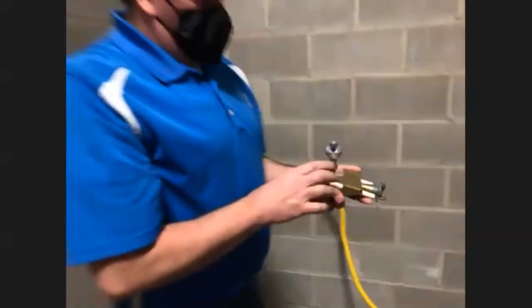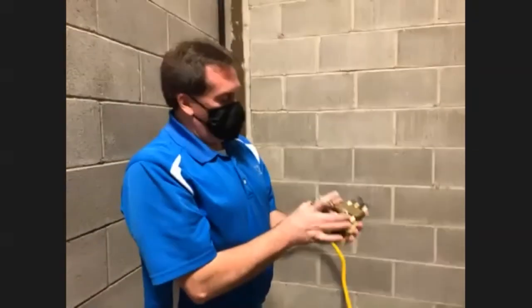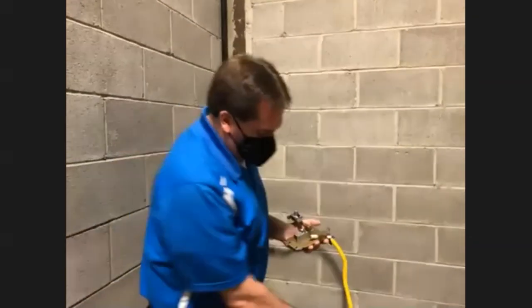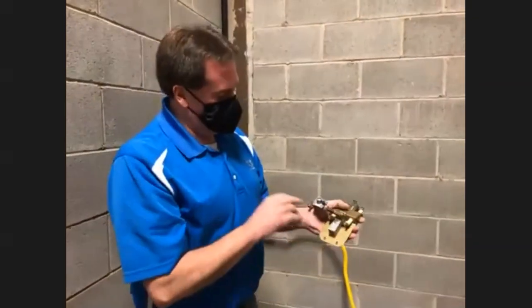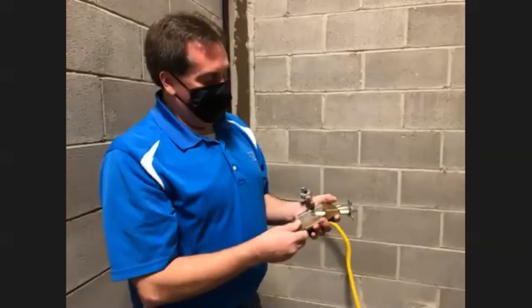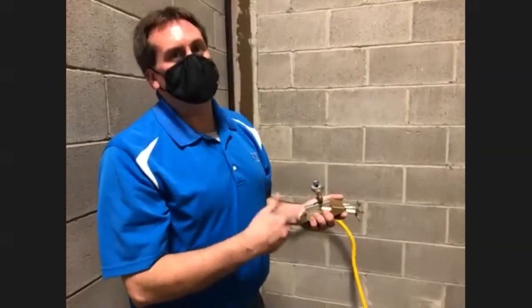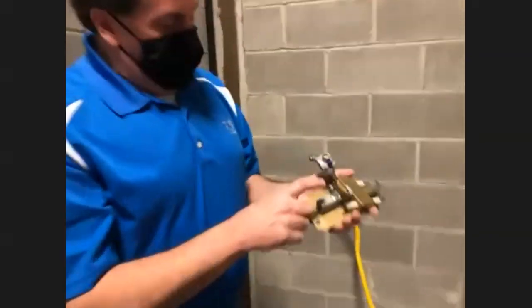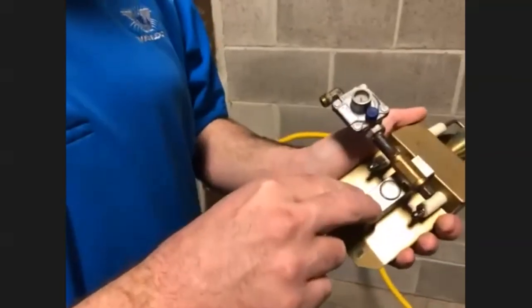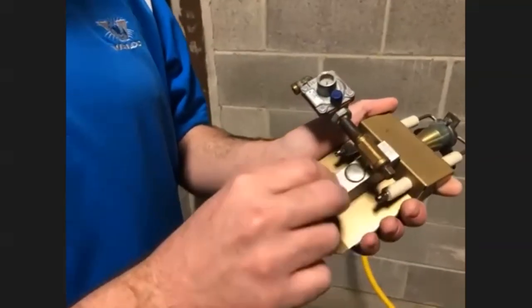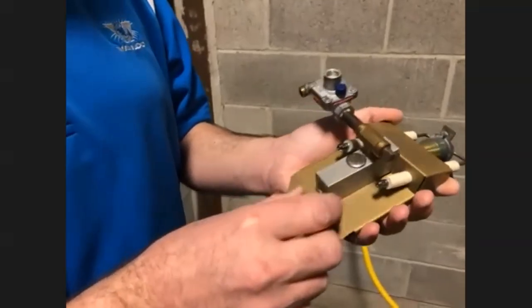If you are still having ignition issues, you verify that your pressures are correct. You have 4 inches coming to this regulator. You have 3.5 coming out. You're still not getting the proper fuel mixture, no combustion. Very well possibly there may be a small particle of dirt or something inside what they call this T-block. It's your orifice assembly, it's your pilot orifice assembly. I have run into that before.